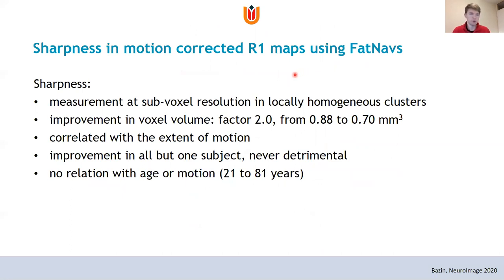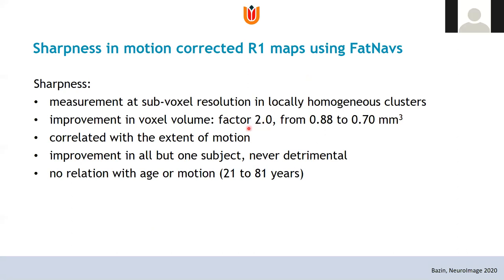This gives us a tool — a measure to use in other applications to actually measure the sharpness in motion-corrected data. The apparent resolution as measured using this approach improves from 0.88 to 0.7 mm³, which is a factor of two reduction in voxel volume. This improvement is visible in our cohort in all subjects but one and is never detrimental. Motion correction matters, and now we have a measure to actually quantify this.